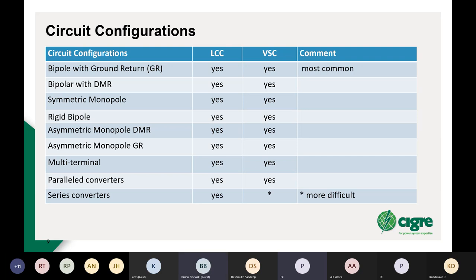So of course, there's a symmetric monopole used mainly with VSC up until this point. There are a few projects though with LCC as well. Rigid bipole, which is an interesting configuration because it doesn't use either metallic return or ground return, but instead requires that you take a short outage if you have a pole fault and then switch the remaining pole to the other line if it's not completely grounded, and you can continue operation then in monopolar with metallic return on the other line pole.